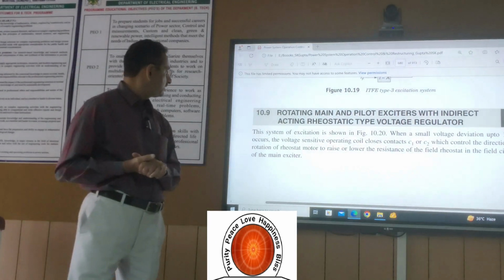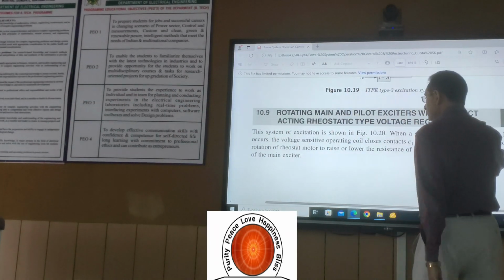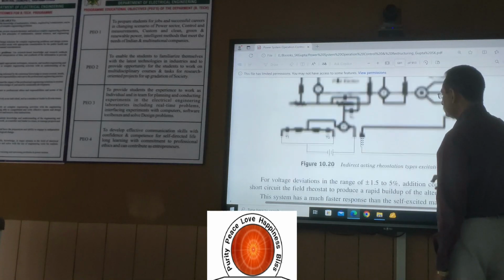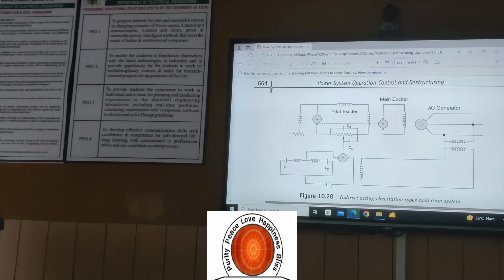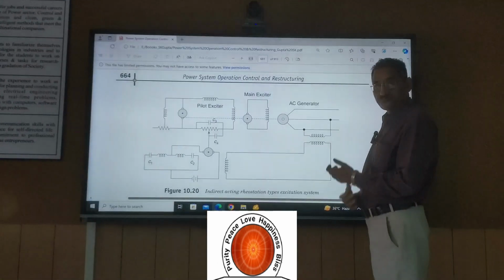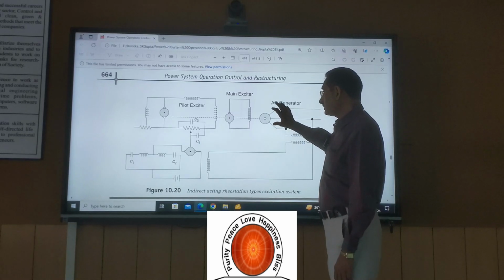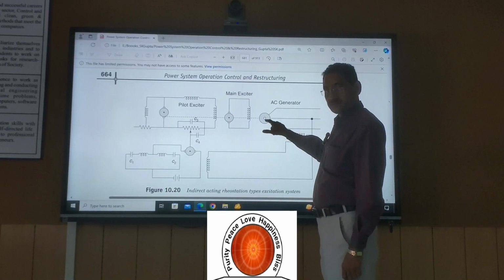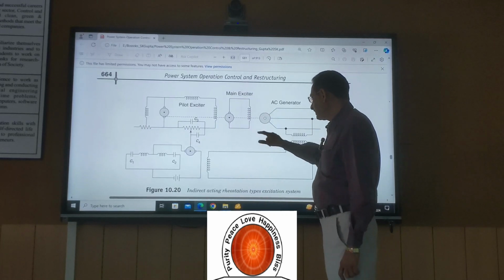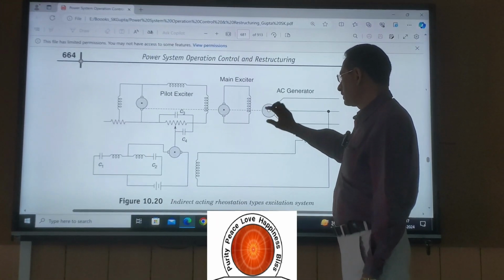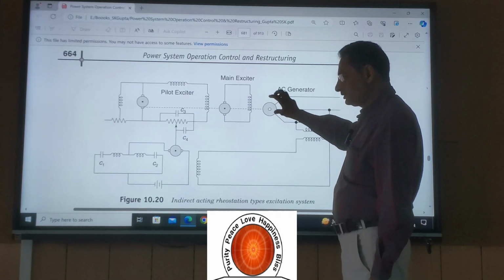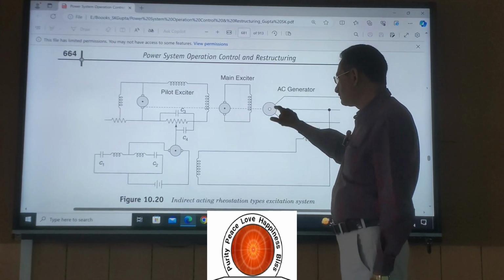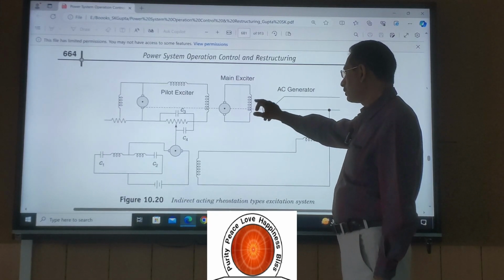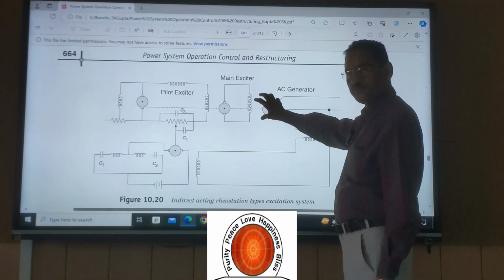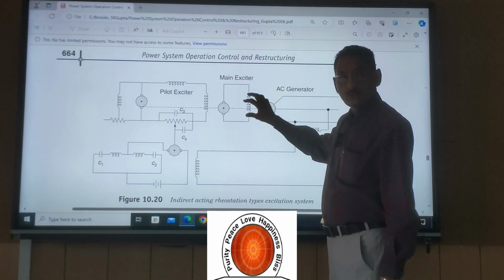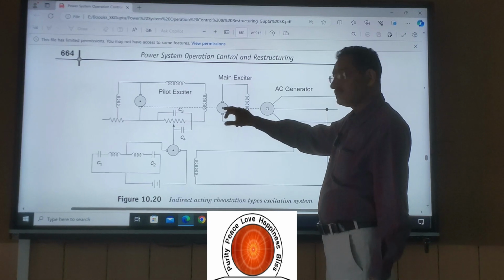That's why the size of this exciter has to be reduced. For that purpose, the size has to be reduced. This is the indirect acting type. So what is the difference between the two? Here it is the main generator, the AC generator. This is the field winding of it. From here to here is the armature, that is the stator, and this is the rotor, which means the field winding of the main AC generator, and it is being excited by this exciter called the main exciter.